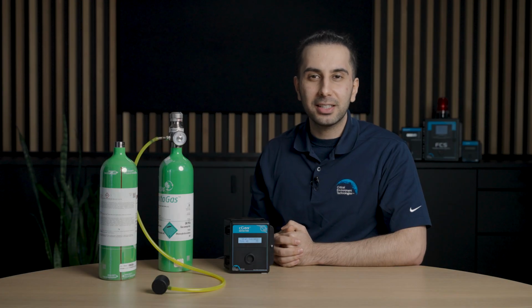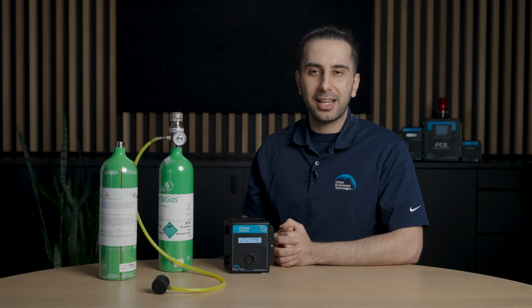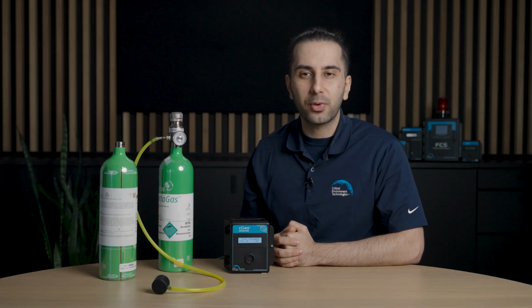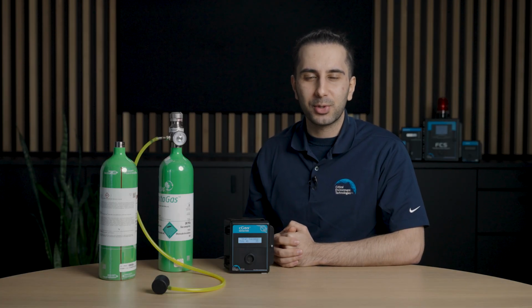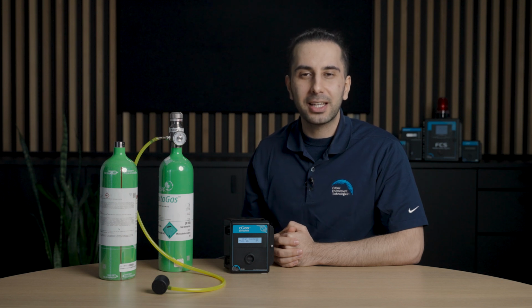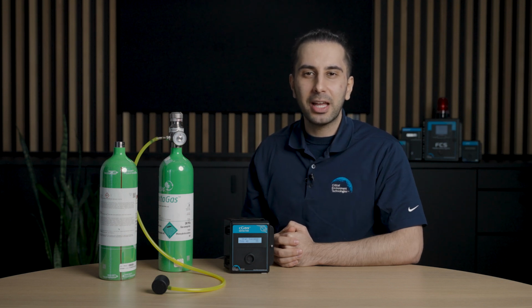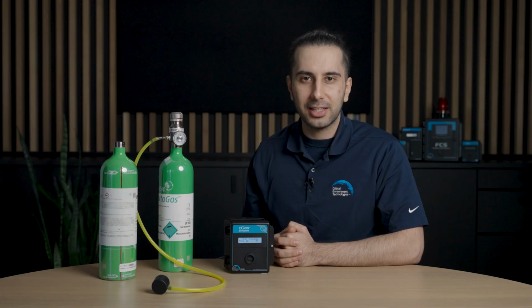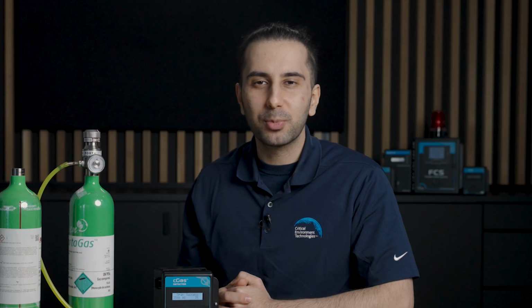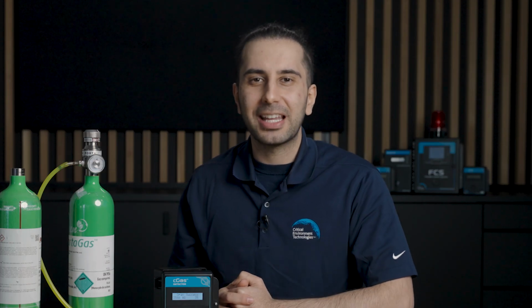If the cGas detector has a second sensor installed, the calibration will have to be performed for the second sensor using the same procedure. After completing calibration, you can apply a label and record the calibration date. And that is how to perform a calibration on the cGas detector.